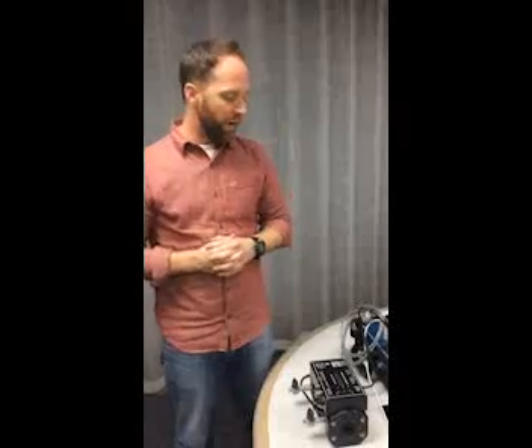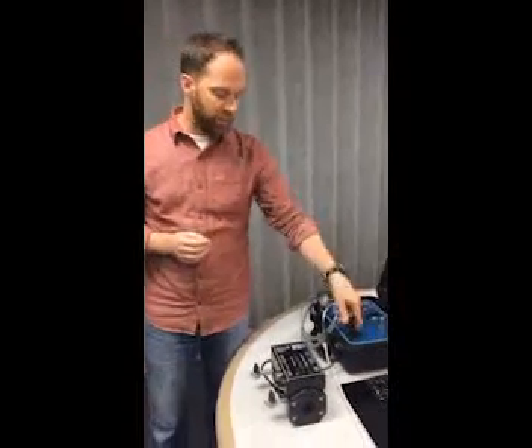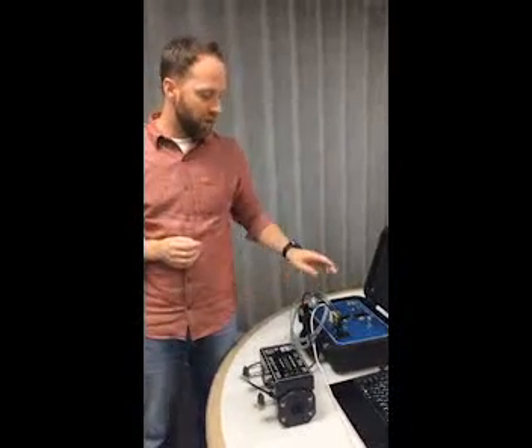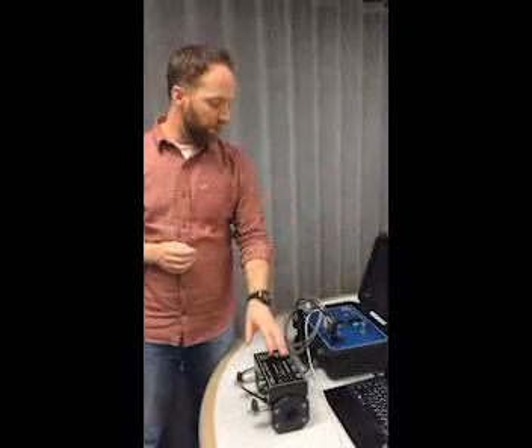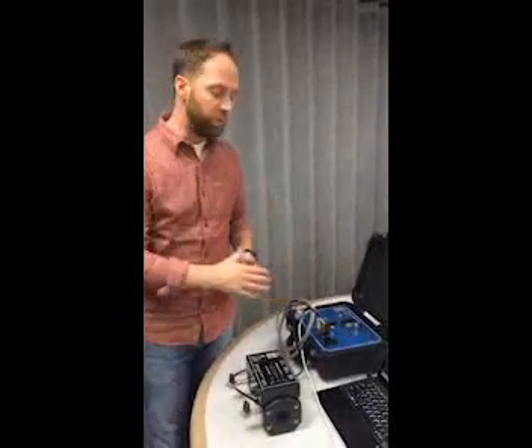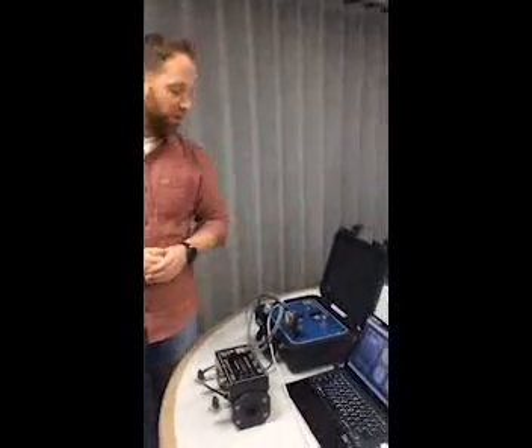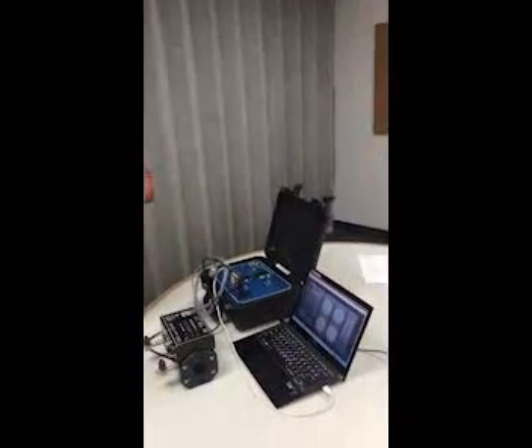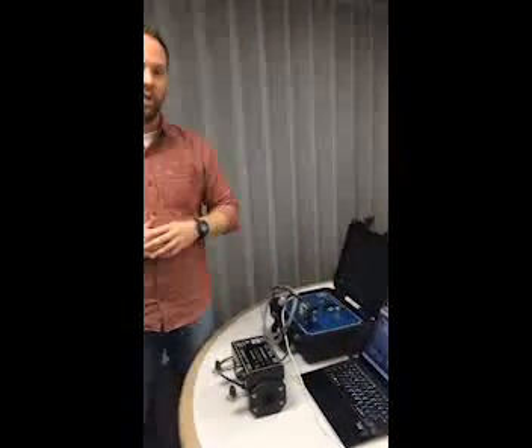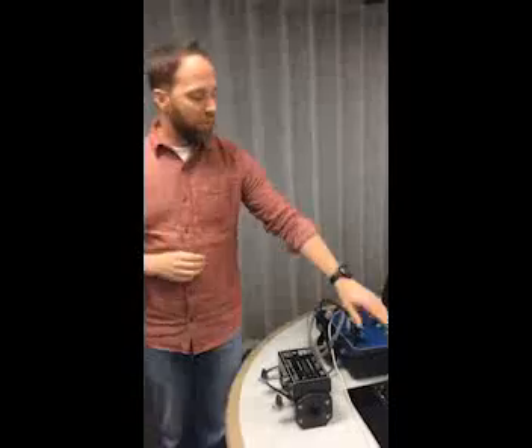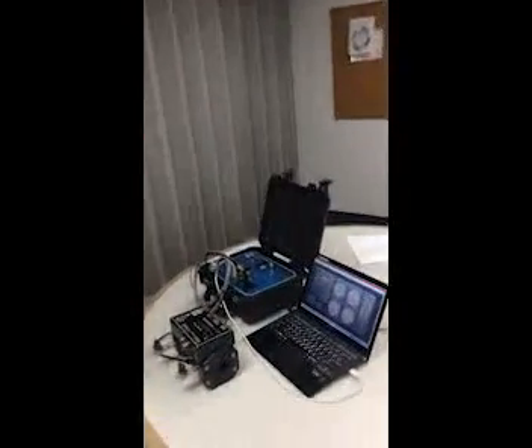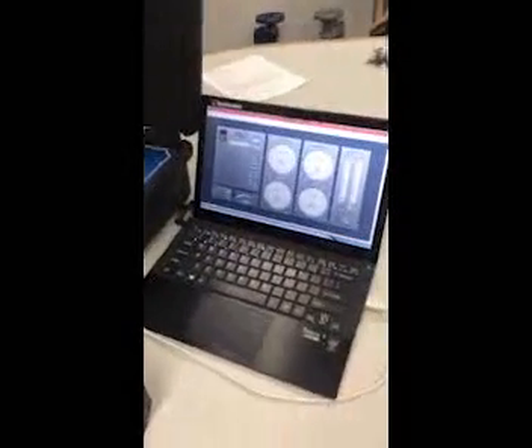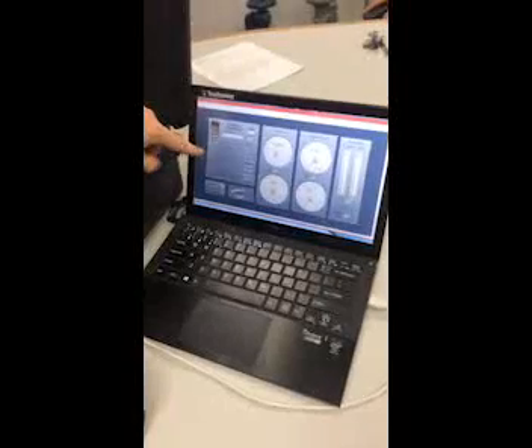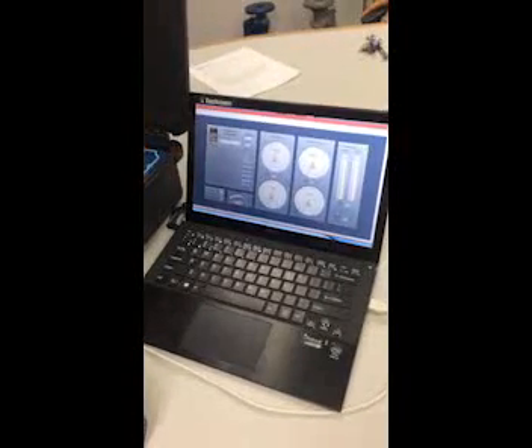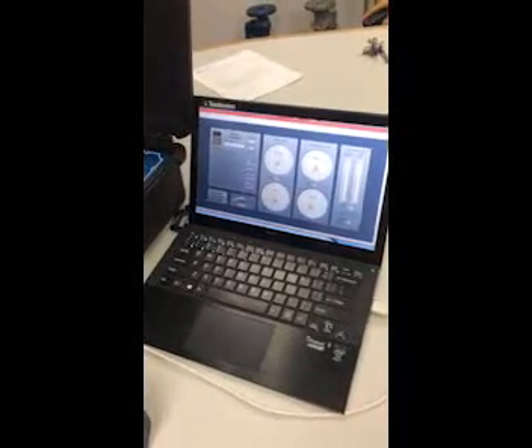Okay, we're almost ready to begin calibrating the FM50. At this point, we have power hooked up to the test set. You can power this unit up as well. Your cable connecting the test set to the flow meter is connected as well. Of course, your USB drive is connected. Your software is installed. The only things not installed yet are those hoses we talked about, and there's a step for that. If you look at your screen now, your installer has completely run, and there are step-by-step instructions on how to calibrate. So we're going to walk you through those steps to get your flow meter performing as best it possibly can.